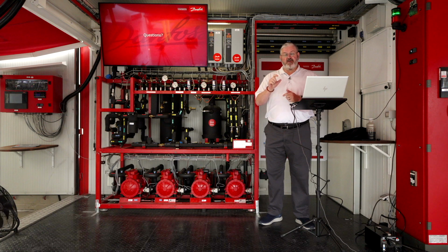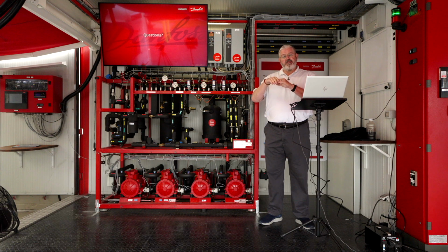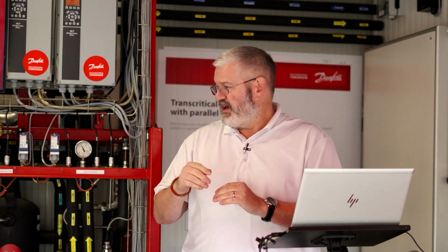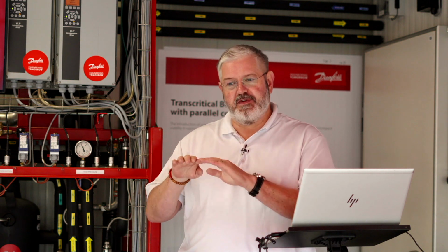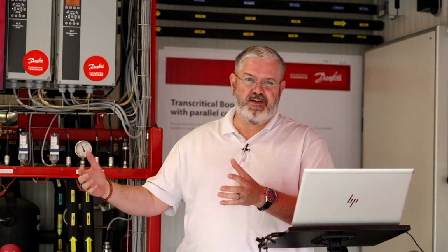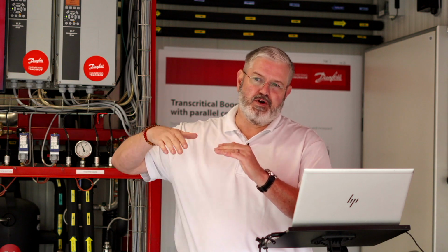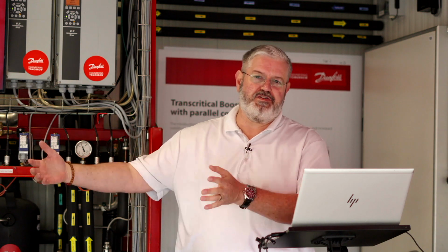A good side of it, though, is that most of them burp. They don't just open and discharge all of your charge. They blow off just enough to where the pressure on the incoming side of the pressure relief is below its set point. So you'll hear a chatter. It almost sounds like a child's little rattler machine gun toy. That means the relief valve is burping. And even if you have to add charge later on a hot day during a startup because you had those sensors swapped, you won't lose the entire charge. You'll just burp charge until you find the problem, and then you would recharge to get it back up to above your bottom side glass.